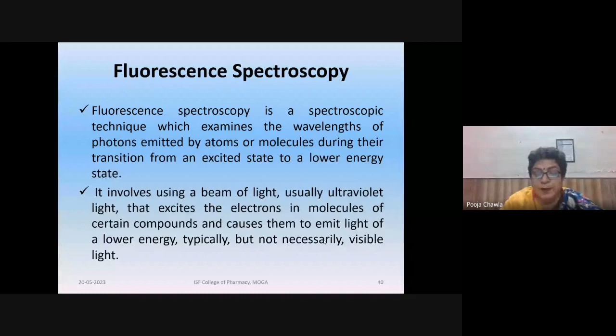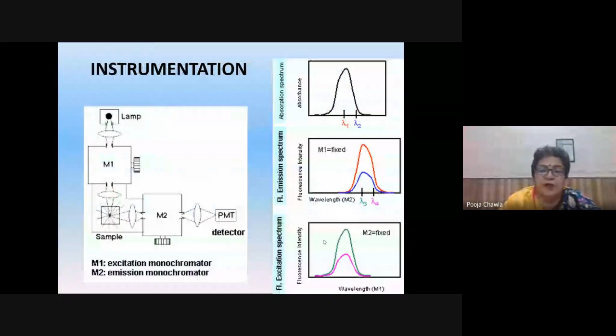Fluorescence is measured by exciting the sample at the absorption wavelength, also called the excitation wavelength, and measuring the emission at a longer wavelength, called the emission or fluorescence wavelength. This is the instrument, the spectrofluorimeter.